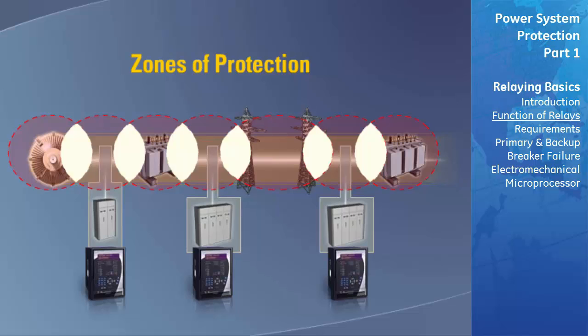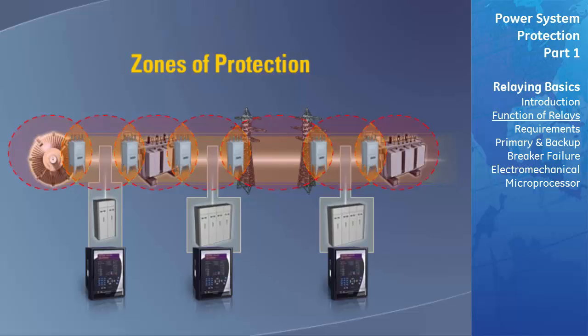For failures within the overlap area, more breakers will be tripped than needed to disconnect the faulty element. However, the overlap areas are relatively small and the probability of failure in this region is very low. Therefore, the tripping of too many breakers for a fault in the overlap area will be infrequent.